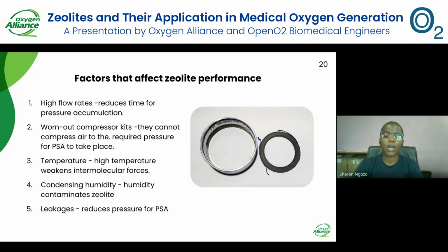If we have kits that are worn out like the ones in the picture, it means it will be really hard for pressure swing adsorption to happen in the sieve beds, because they will not be producing enough pressure for the process to happen.